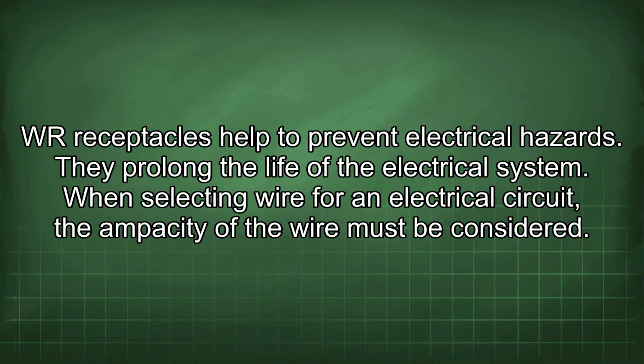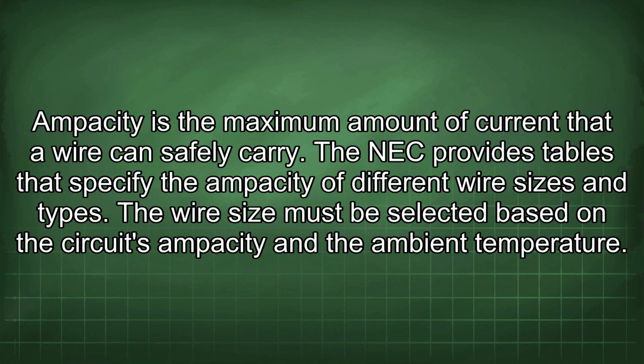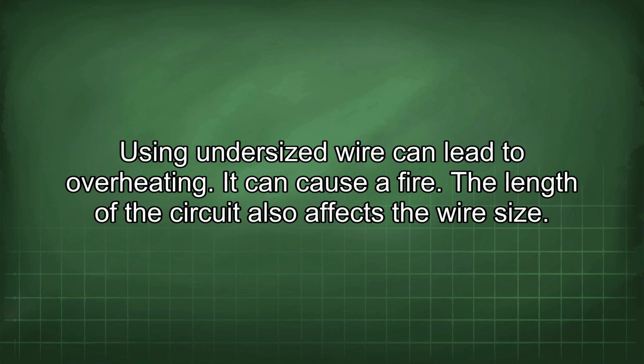When selecting wire for an electrical circuit, the ampacity of the wire must be considered. Ampacity is the maximum amount of current that a wire can safely carry. The NEC provides tables that specify the ampacity of different wire sizes and types. The wire size must be selected based on the circuit's ampacity and the ambient temperature. Using undersized wire can lead to overheating. It can cause a fire.